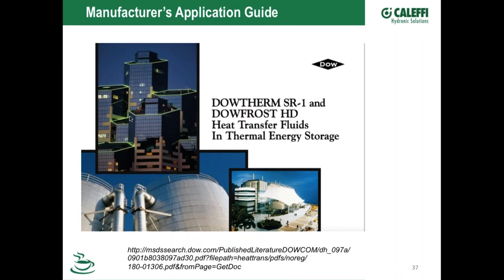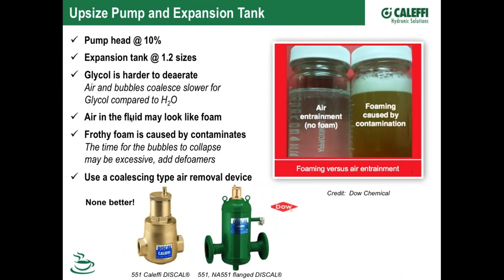A good example here. This slide is from Kevin Connor's presentation, that's why it's got the Dow logo on it. He said be aware of your pump head, and also be aware of your expansion tank sizing with glycols, because you need about 1.2 times bigger size for your expansion due to that viscosity and fluid expansion when heated.